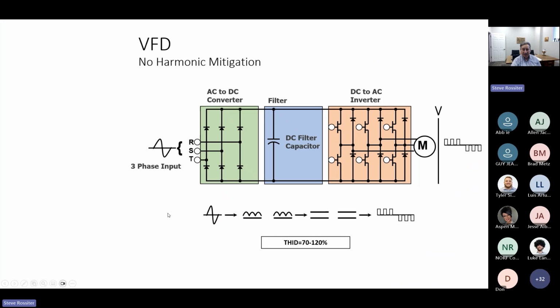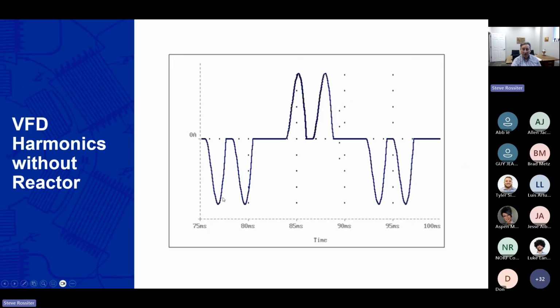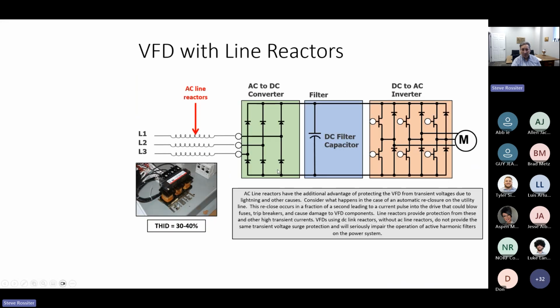Here's an example of a typical PWM 6-pulse variable frequency drive with no impedance on the line side. And that would typically come up to 70 to 120%. And again, that's because of that gulping effect that's coming back through here, and there being no impedance like a line reactor, which is why the waveform is even discontinuous. It goes all the way back down to 0. That's that typical double hump. We don't like to see that very often. Small micro drives, maybe not a problem, but the larger the drive or the load becomes, the more problematic.